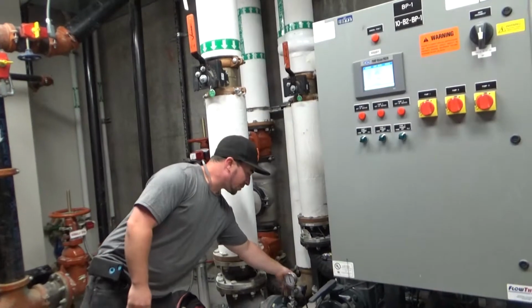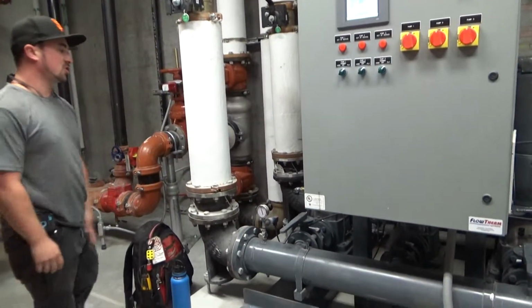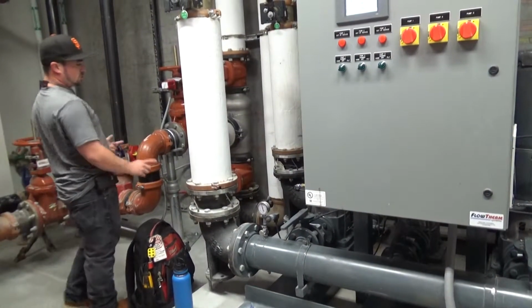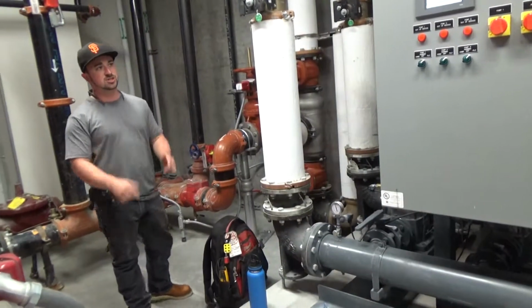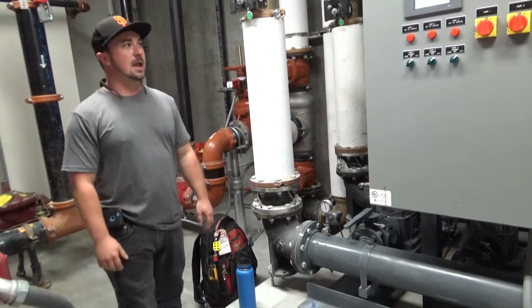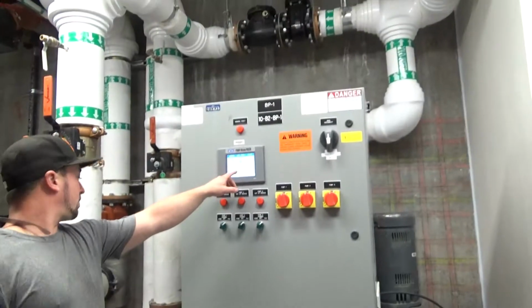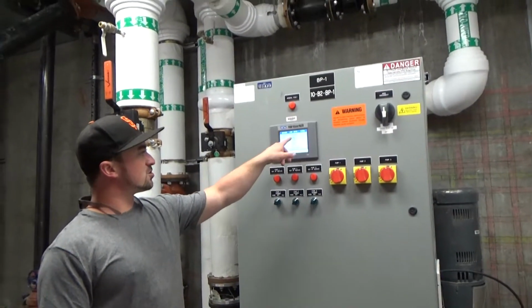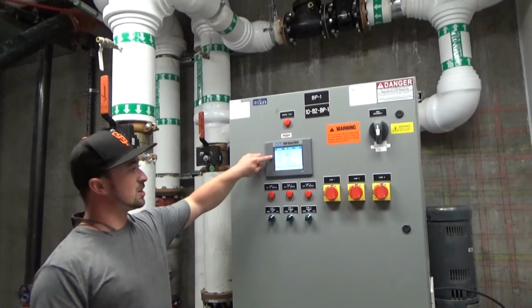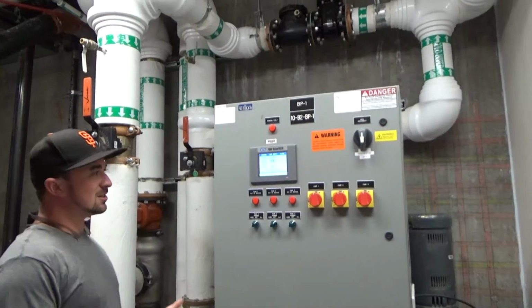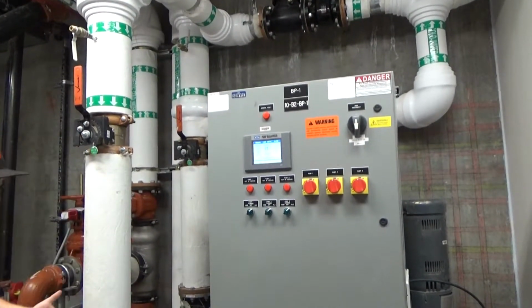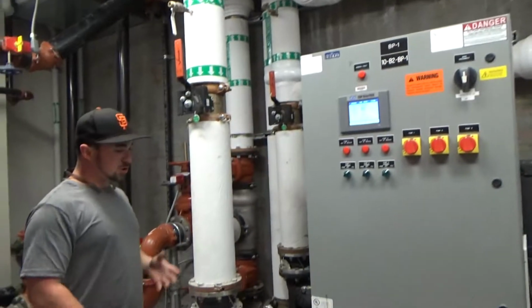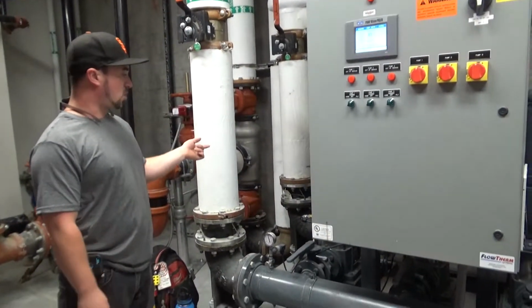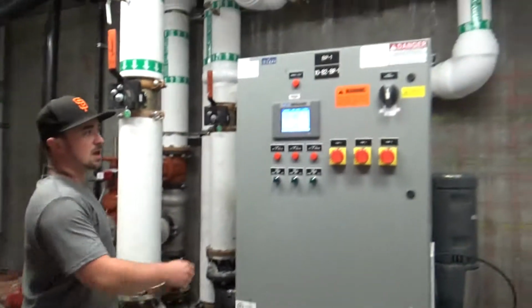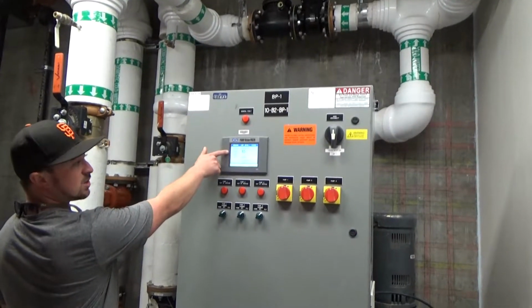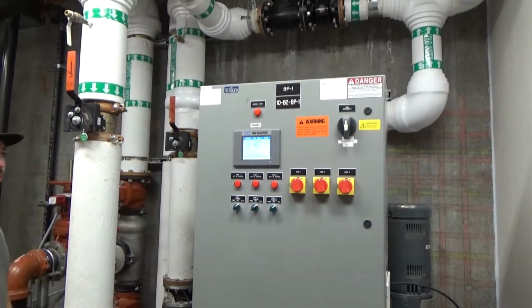To back it up, you have a transducer on your discharge and your suction piping. What those transducers are doing is sending a pressure signal back to the control panel. And so your pressure on your suction is 85 and your system is 85. And your set point's 85. So technically, this booster is not doing much. I'm assuming the only purpose of this booster is that if the city water drops pretty low, like maybe 60, and you guys still want 85, that's when these pumps are going to come on.